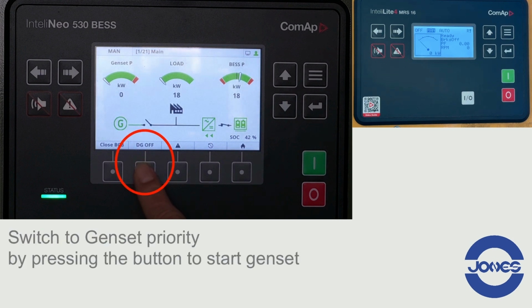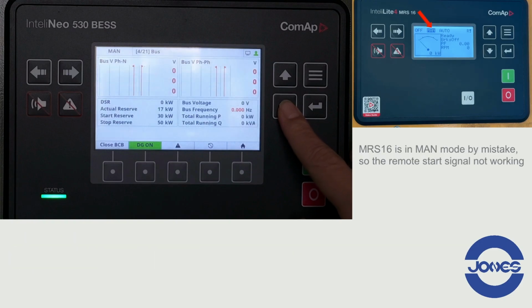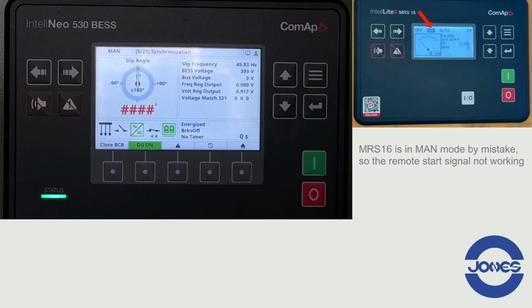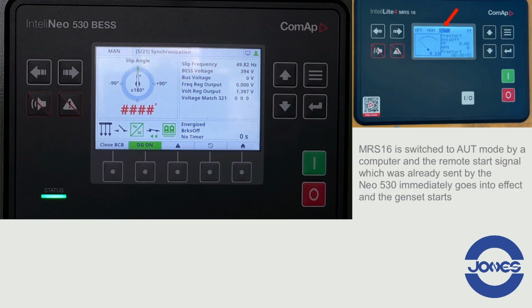We will switch to Genset Priority by pressing the button to start the genset. The MRS16 is in man mode by mistake, so the remote start signal is not working. The MRS16 is switched to auto mode by computer, and the remote start signal, which was already sent by the Neo 530, immediately goes into effect, and the genset starts.